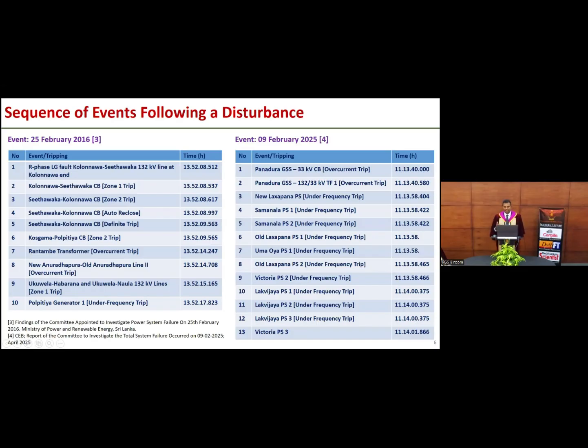And the second scenario is the famous monkey event which happened last year. Because of that situation, one of the transformers in the grid substation failed, and which triggered cascading events. And we can clearly see that a number of generator units went out from the system due to frequency issues. So the two things that I want to highlight from this slide are that a single fault can trigger a number of cascading events unless you take control actions on time, and also look at the time of interest in this particular domain of analysis. It's in the seconds. So when it comes to transient stability assessment in power systems, we have to take actions as quickly as possible to secure at least part of a power system.